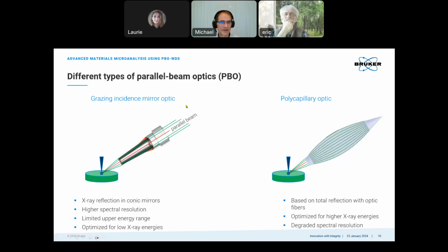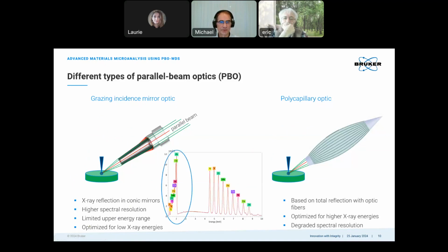There are different types of parallel beam optics available. Two end members are the Grazing Incidence optic on the left side, and on the right side, the polycapillary optic using optic fibers. Bruker is using the Grazing Incidence optic, where conic metallic mirrors reflect the diverging X-rays and convert them into a parallel beam. The advantage of such a system is the very high spectral resolution compared to other parallel beam optic systems. It has a lower transmission for the high energy X-rays, but it's optimized for the low energy X-rays. And this is what is most crucial.